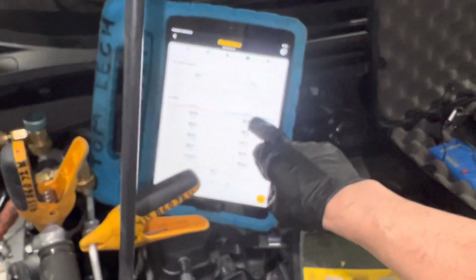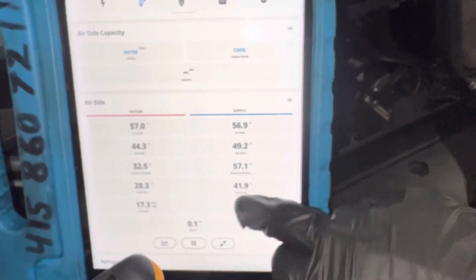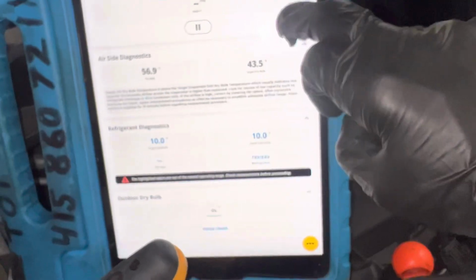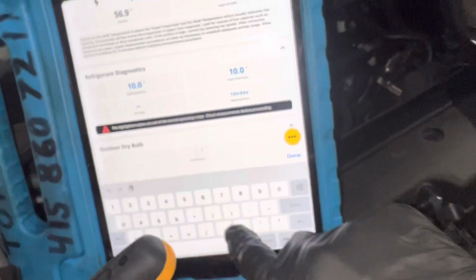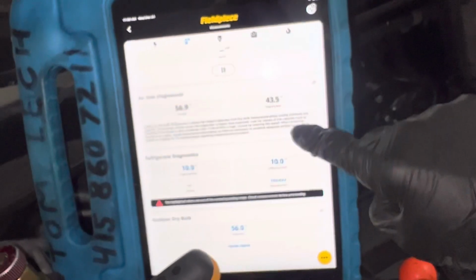So we're now filled, let's start this guy up. Our outside ambient temperature right now is 56 degrees, if you can see that. Our refrigerant should already be in there — yeah, 56. I don't have my temperature sensor hooked up to this automatically, so I manually put in the temperature. Let's start data logging.